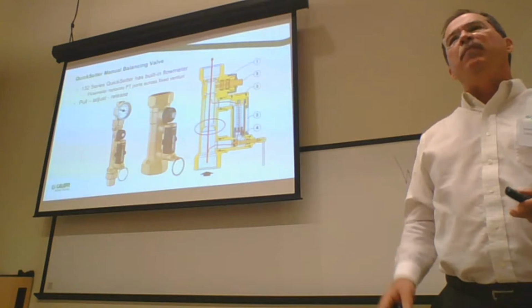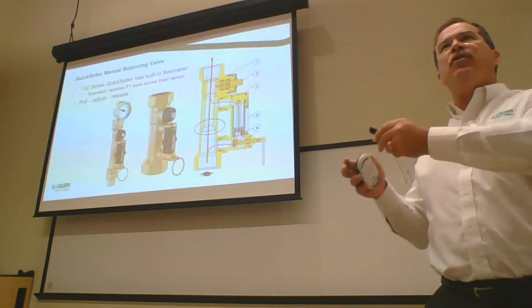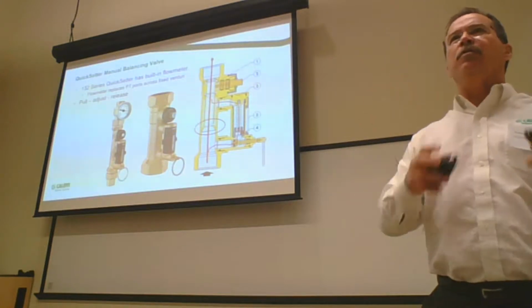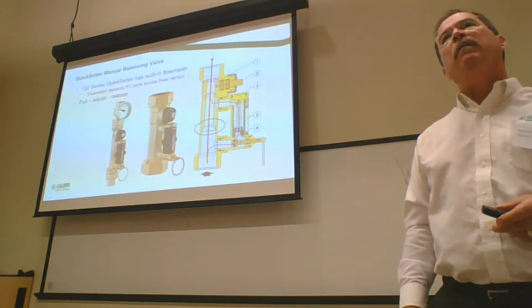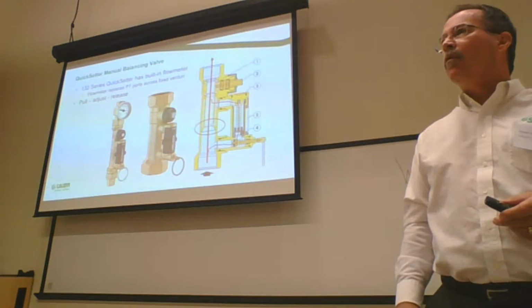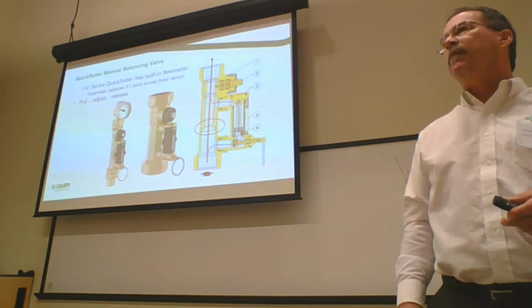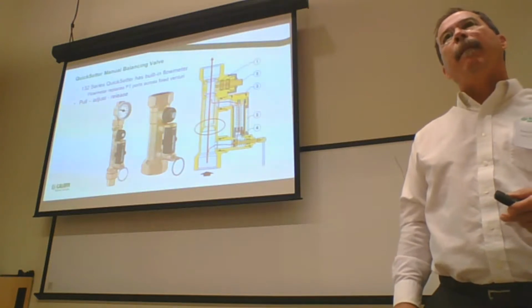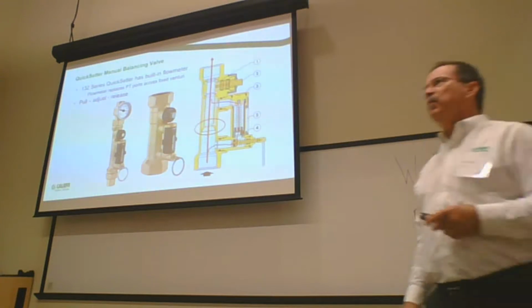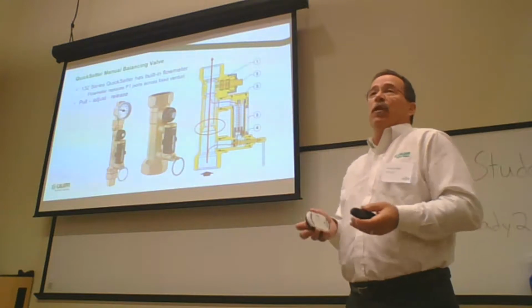Okay, good point. So because you're using a tool that's calibrated, you can then read that GPM with your meter, and you can certify. And you're verifying that that's 3 gallons. Right, without a PT, without a port to plug into, how do we verify that it is accurate? Okay, good point. We have our instrument to guarantee the meter. So you wouldn't be able to use one of these and then make it a test and balance report because you don't have a way to certify.